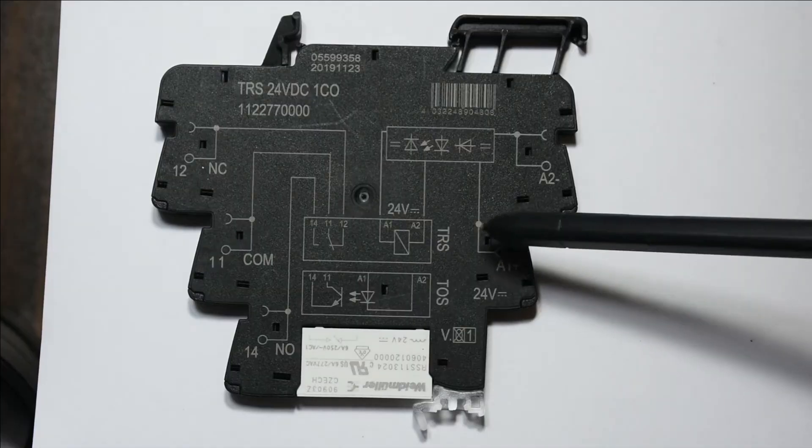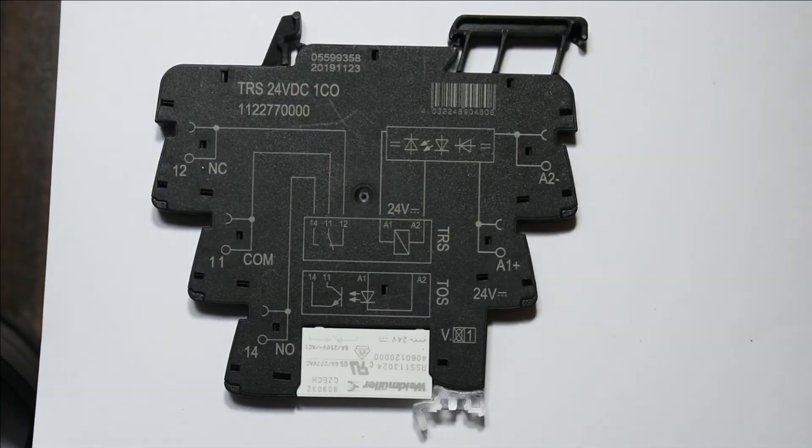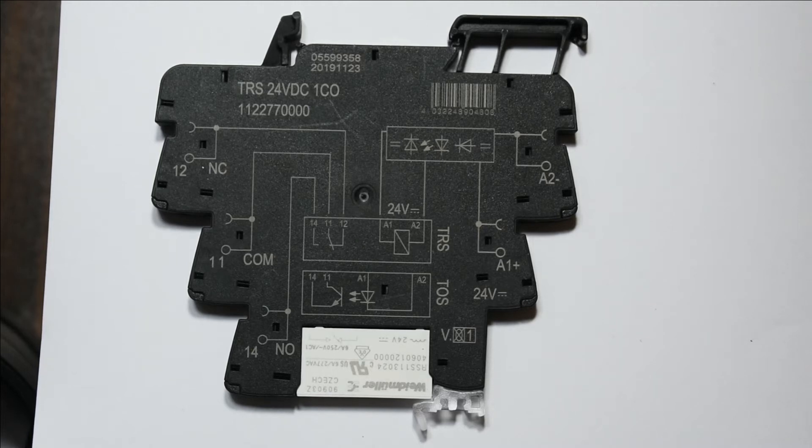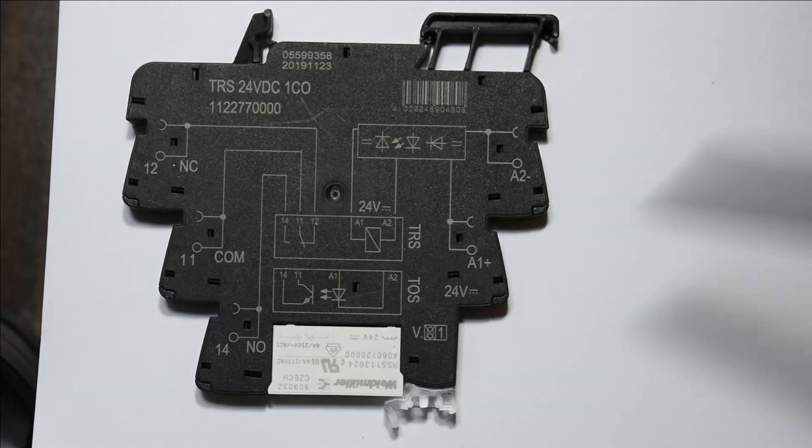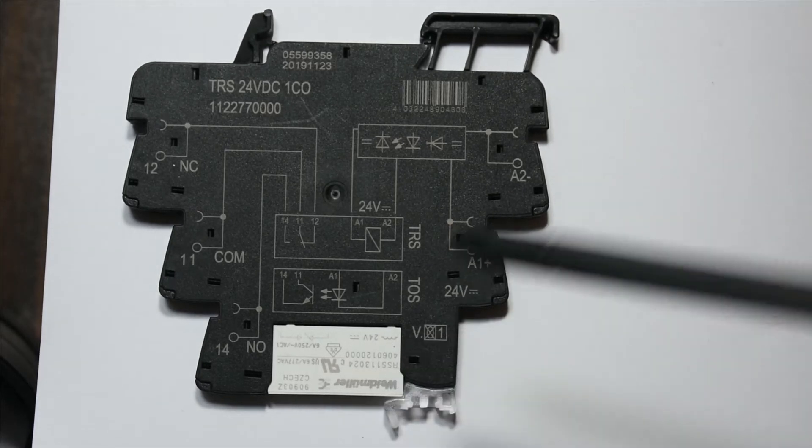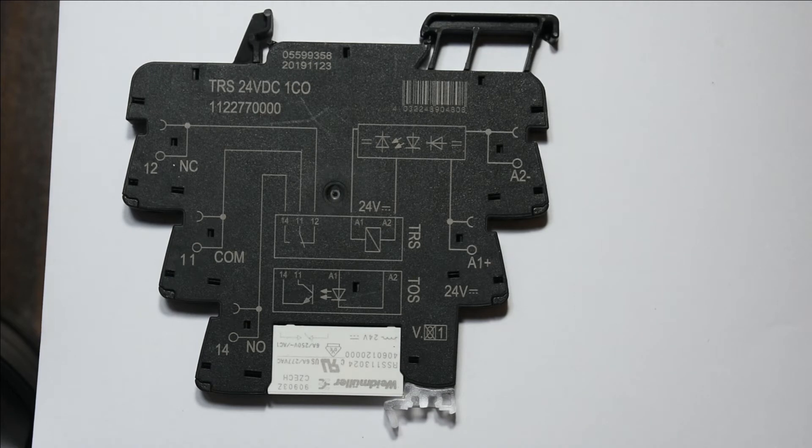These relays are normally used as signal relays. Why? Because they are not able to conduct a large amount of current. This relay is rated up to 6 amps, 240 volts.